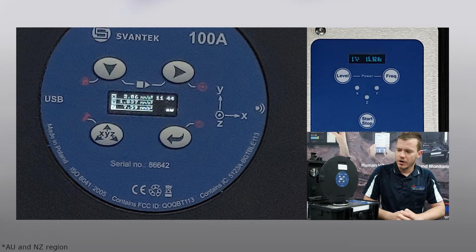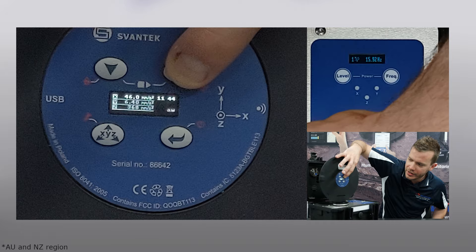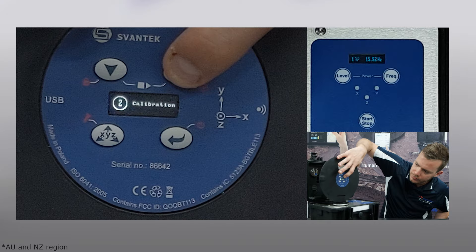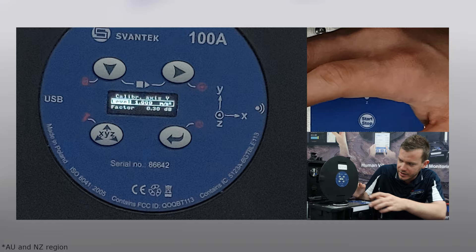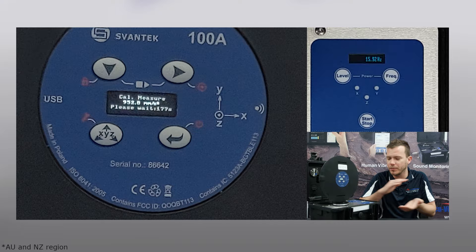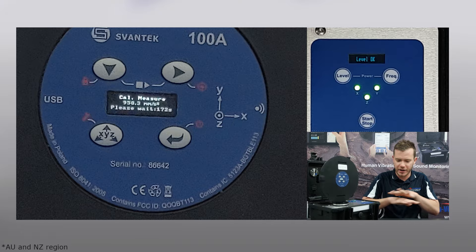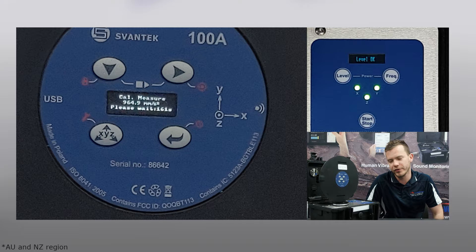Once we've re-orientated the seat pad, this is in the Y axis now. Same thing applies - holding the calibration menu on the top right. By measurement, enter, and I'm going to go up this time to Y axis. As I mentioned, five second delay, so I'm going to press start. That's my level. Press start and I'm going to start the shaker, and once again you can see it's auto leveling. We're going to get green lights. If you're in the field and one of these lights is red, it's probably because of what you're mounting it on or what table you're using. Just stay away from the actual surface and let it do its own thing. Now it's all green lights. Once again, we've got 160 seconds to go, so just wait for it to do its internal calibration.